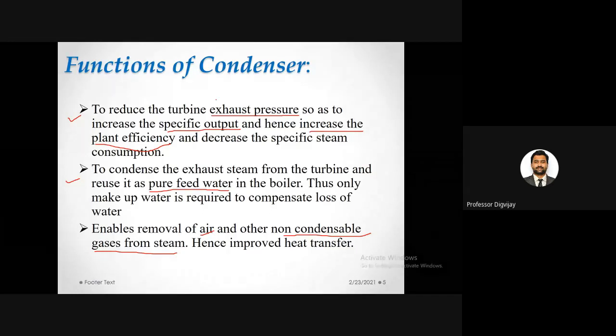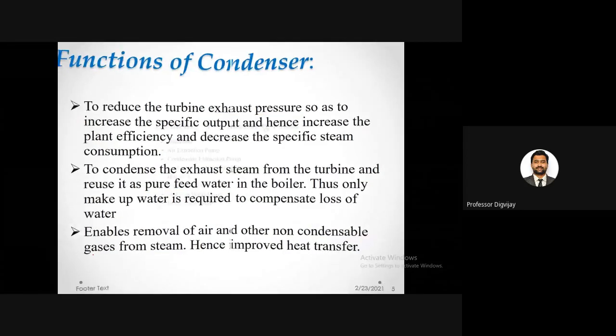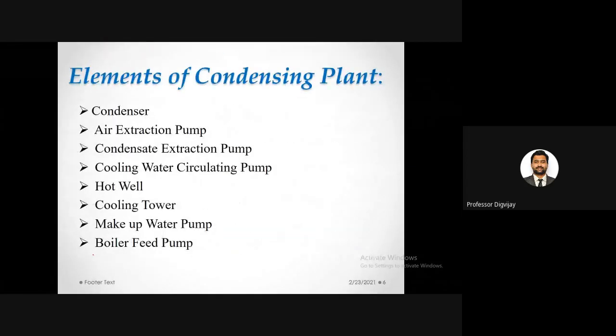Okay, so there are three functions of this condenser: to reduce the turbine's exhaust pressure, increase the plant efficiency, decrease the specific steam consumption. This was the first one. Second was to condense the exhaust steam and reuse it as pure feed water. Third was to remove the air and non-condensable gases from the steam. So these are the three functions of the condenser. Right. So already I have explained.